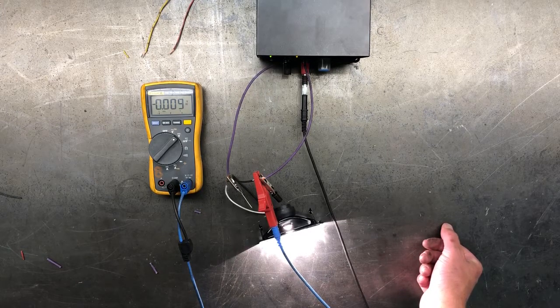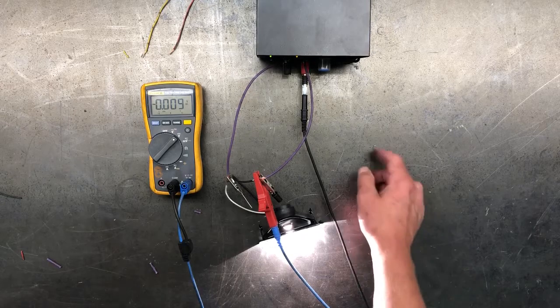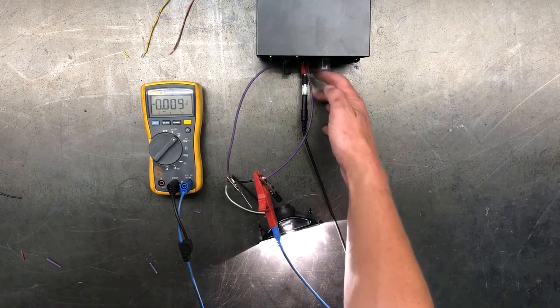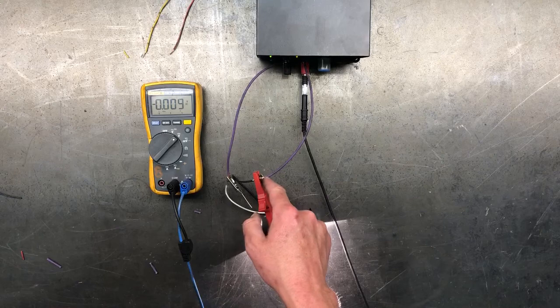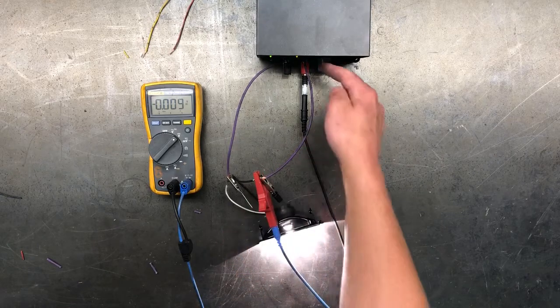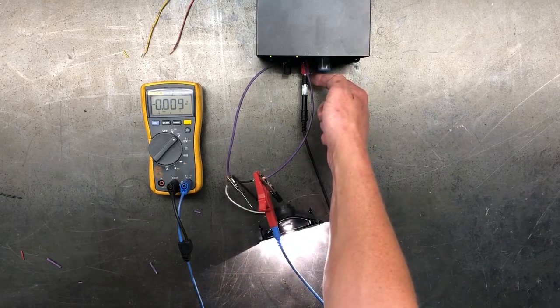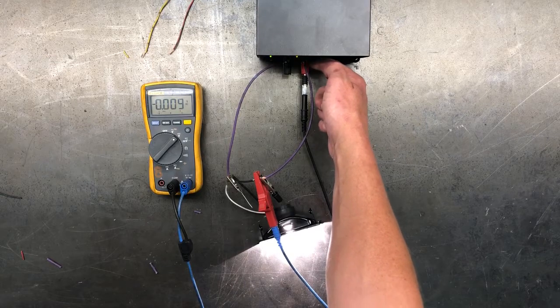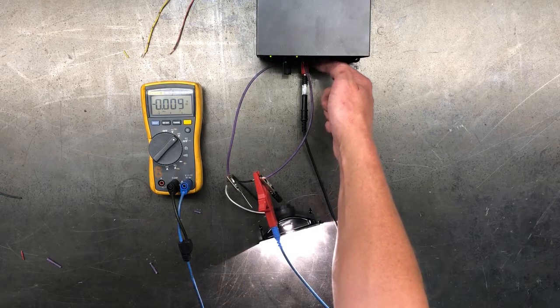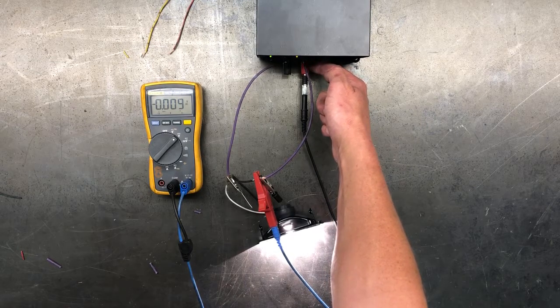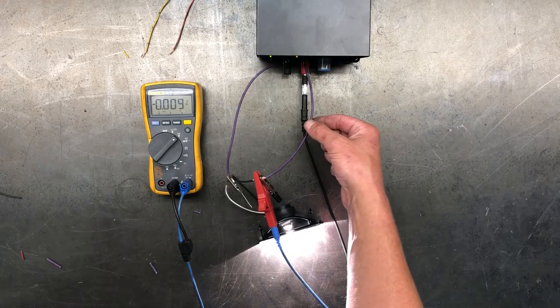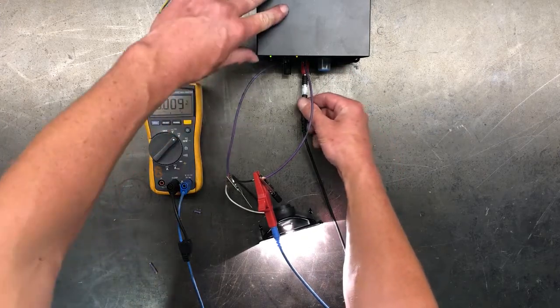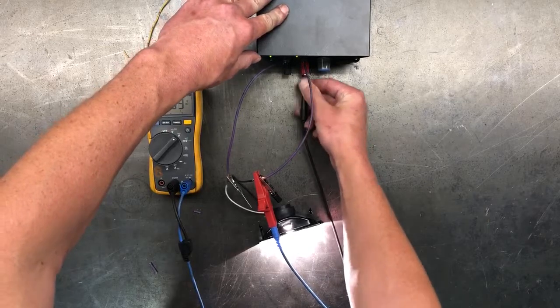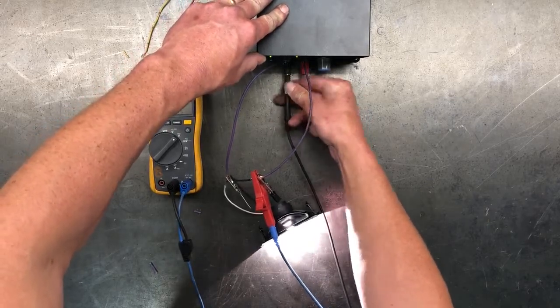If you're voltage drop testing, you want to try and be on each end of the cable. Because if you're on the other side of this connection here, or the other side of this connection here, you could be picking up a volt drop that is between the wire and this thumb screw, and not necessarily the wire itself. So let's come back over here real quick to our negative lead.